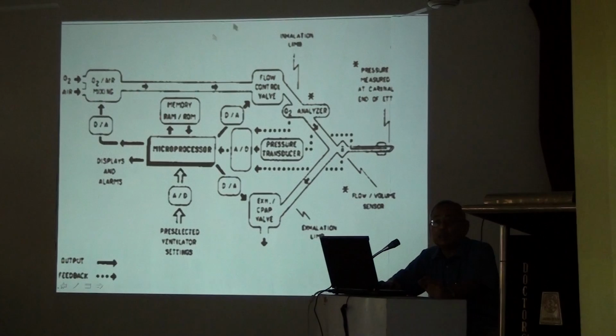Now comes the inside of the machinery. Nowadays, most of the machines are electronically controlled machines. There is a microprocessor inside. Now you have the controls. You can have control on the machine. You can put your desired values. Say I want 500 ml tidal volume, 12 respiratory rate, and some flow pattern and all these things. From very basic, these two things, and the pressure. Target is the pressure. How much inflation pressure?